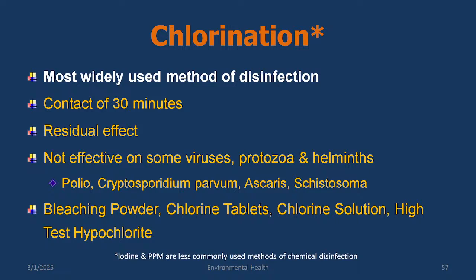Cheaper. So it needs a contact of 30 minutes. There is a residual effect. Residual effect means once the disinfection has happened, there is residual chlorine in water, and that will prevent further contamination by bacteriological or other viral agents or other biological agents till a certain limit. It doesn't mean that you put a lot of fecal matter and then it remains disinfected. It's not like that, but it protects for a longer duration. And even that, it is not effective for some viruses, protozoa, especially helminths. It doesn't kill the helminth eggs.